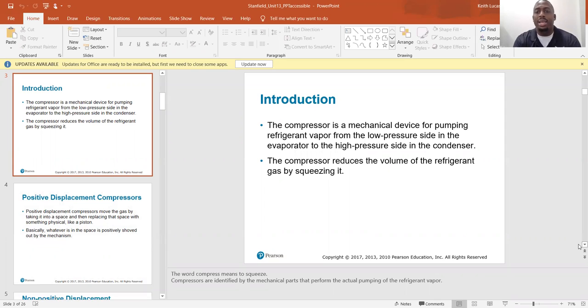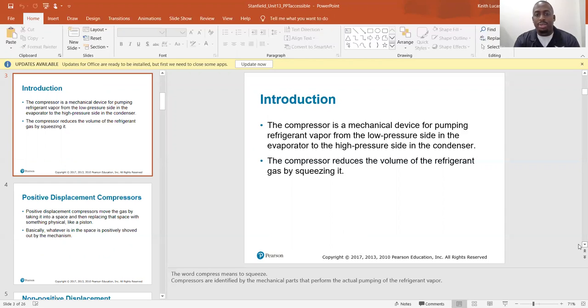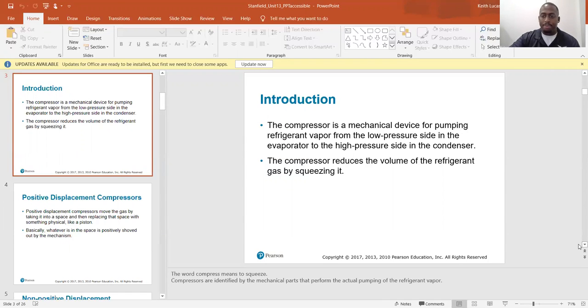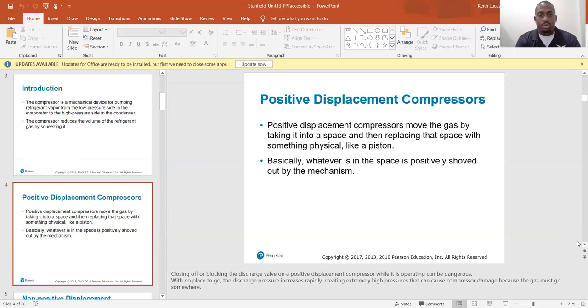The compressor is a mechanical device for pumping refrigerant vapor from the low pressure side of the evaporator to the high pressure side in the condenser. It reduces the volume of the refrigerant gas by squeezing it, creating higher pressure. One key thing to note: compressors pump refrigerant vapor — they are vapor pumps, not liquid pumps. Compressors and liquid do not mix; you will break your compressor if you allow liquid into it, which is why correct refrigerant charge is so important.